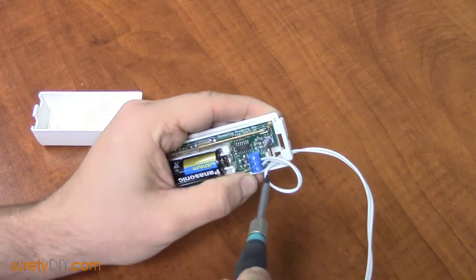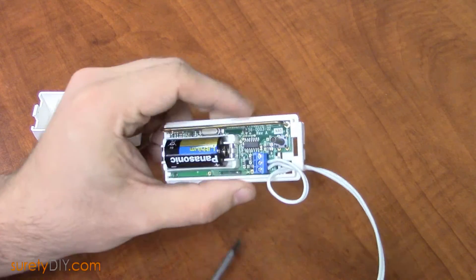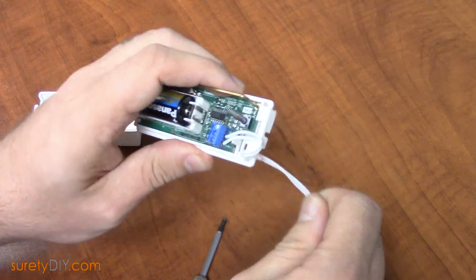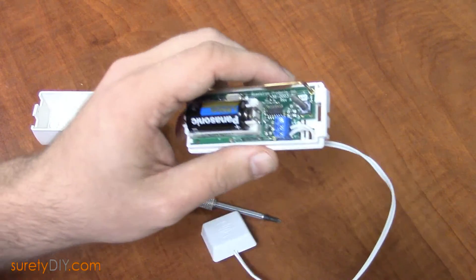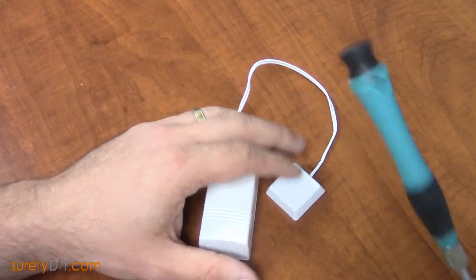Pass the wires into the casing for your sensor and attach them to the terminal block. In this case, I'm using A and ground on the RE-201, which corresponds to loop 1 in programming, while the open-close-reed switch on the sensor itself is loop 2.